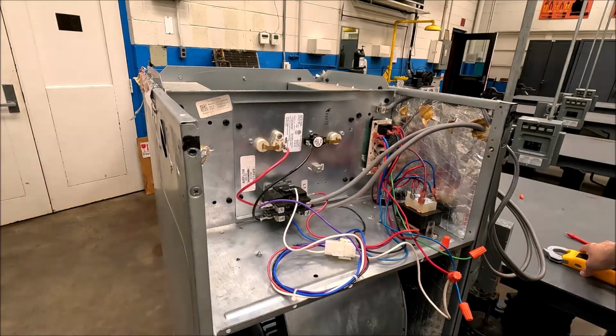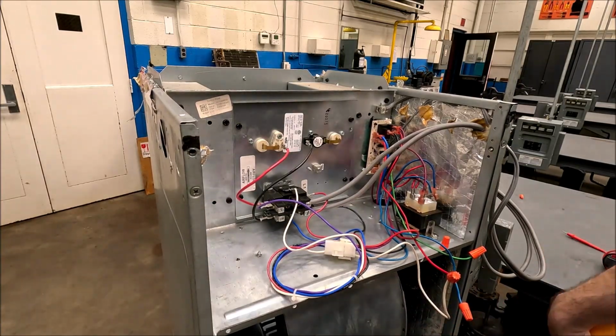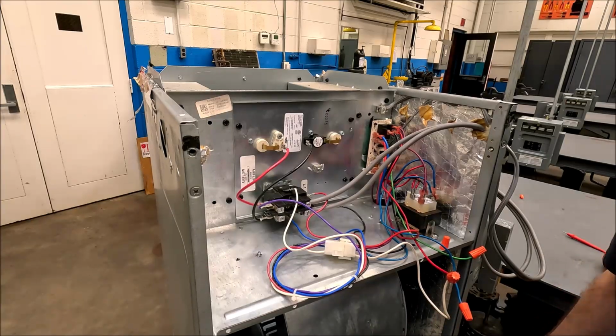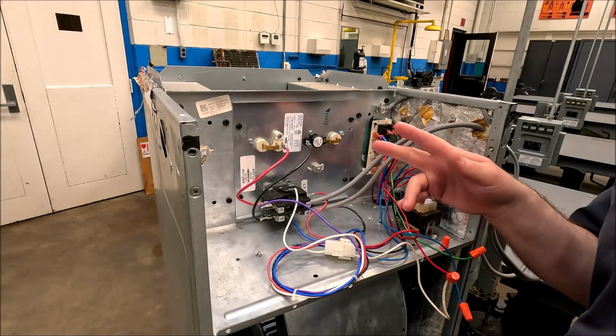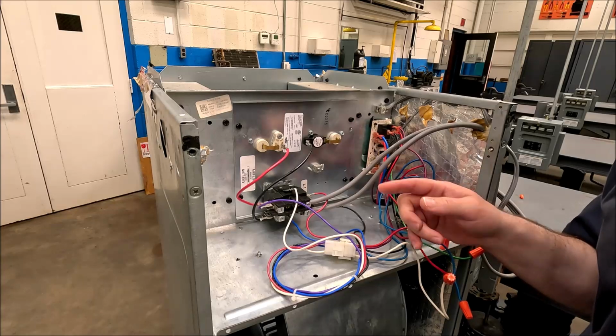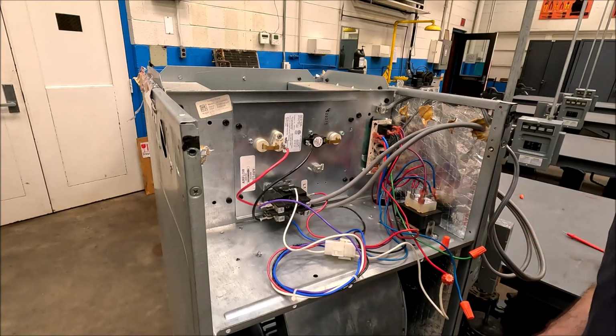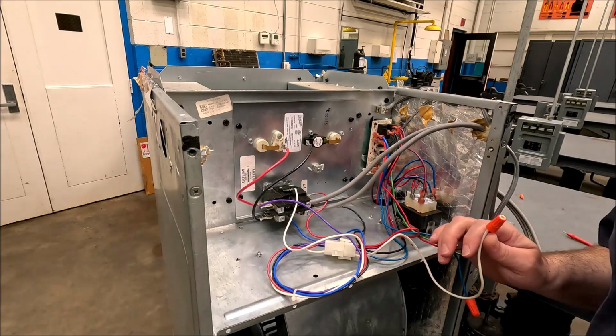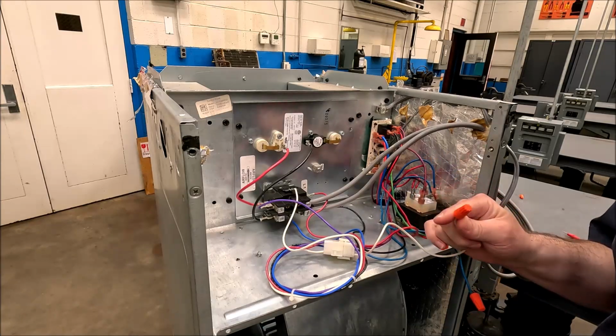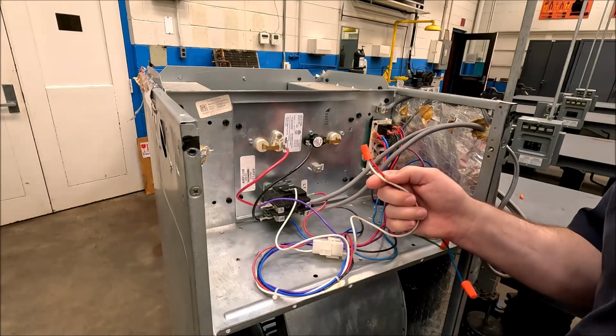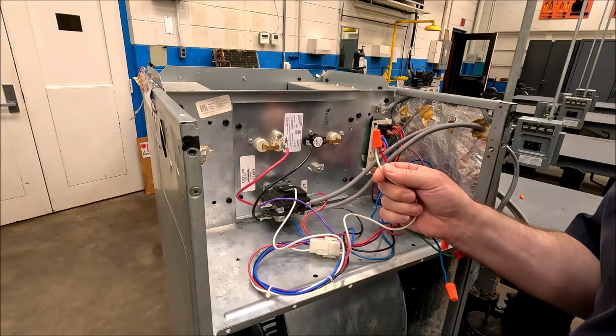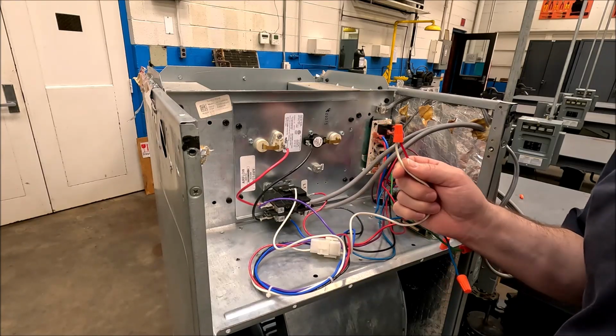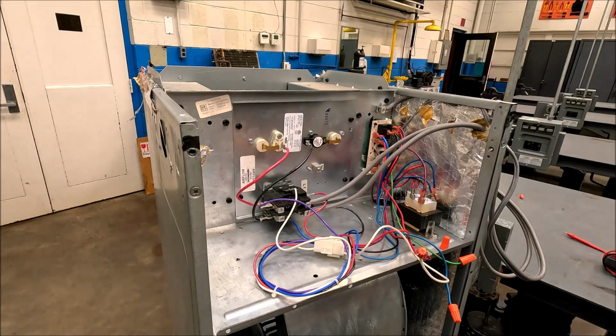All right, so last setup for the day. Like I said, this is all residential based anyway. So what I've got here is my heater kit and a PSC motor in here. Because we were going to toss this air handler and replace it with a new one, we don't have a thermostat on it. I've just taken and wire nutted the red to the white so I can get the contactor to pull on.